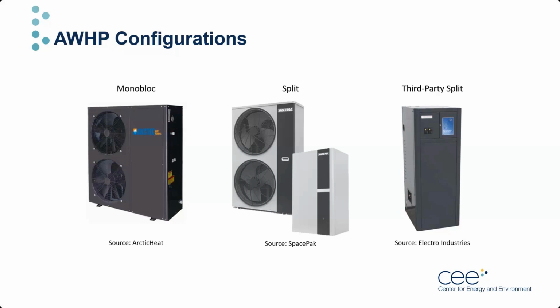The split-type air-to-water heat pump system has an additional subcategory that we call third-party split. This is an AWHP system that is sold as an IDU-only solution, much like a traditional electric boiler, but that is designed to interface with a traditional third-party air source heat pump as the outdoor unit. So that image on the right just shows the IDU, and you would pair that with your favorite non-communicating outdoor unit.